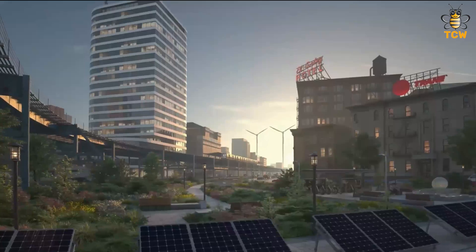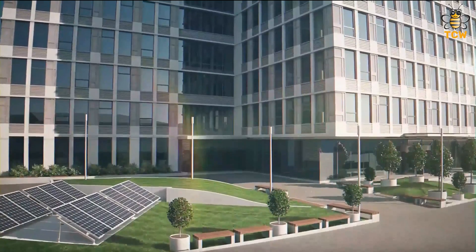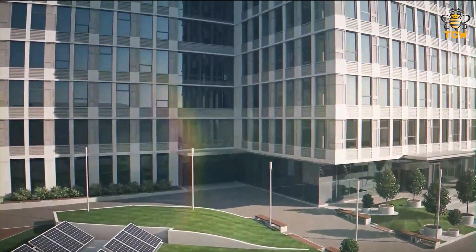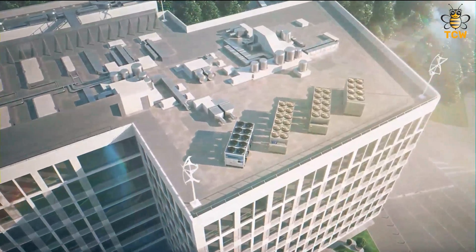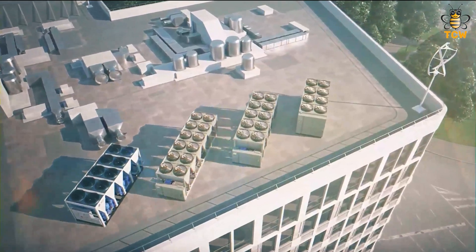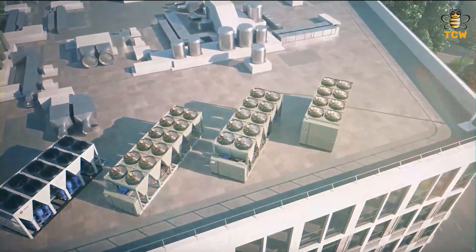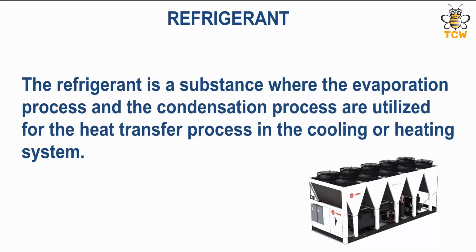In the world of air conditioning, there are two types of chillers used: water-cooled chiller and air-cooled chiller. The difference is the fluid used to release heat in the condenser, where the water-cooled chiller uses water and the air-cooled chiller uses air. Air-cooled chiller removes heat from the chilled water using outdoor air directly, and is usually placed at the top of the building. The refrigerant is a substance where the evaporation and condensation processes are utilized for heat transfer in the cooling or heating system.